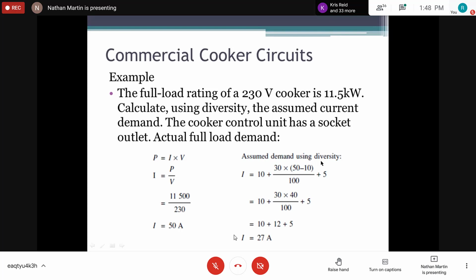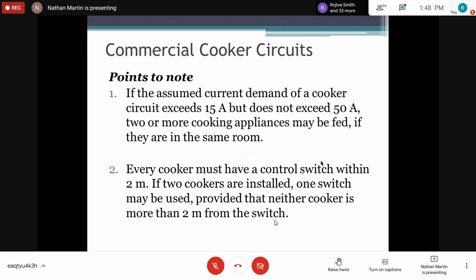Now, what we are saying is that most of the time, this appliance will be drawing 27 amps, right? So rather than sizing the cable for this 50 amp, which will be a very large cable compared to that of the 27 amp, rather than using probably a 10 millimeter cable, we can use our 4 millimeter cable to run our commercial cooker. All right, so that's really applying our diversity factor in this case.